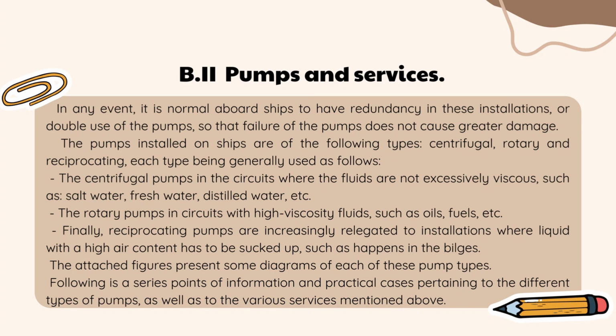The pumps installed on ships are of the following types: centrifugal, rotary and reciprocating, each type being generally used as follows. The centrifugal pumps in the circuits where the fluids are not excessively viscous, such as salt water, fresh water, distilled water, etc. The rotary pumps in circuits with high viscosity fluids, such as oils, fuels, etc. Finally, reciprocating pumps are increasingly relegated to installations where liquid with a high air content has to be sucked up, such as happens in the bilges.